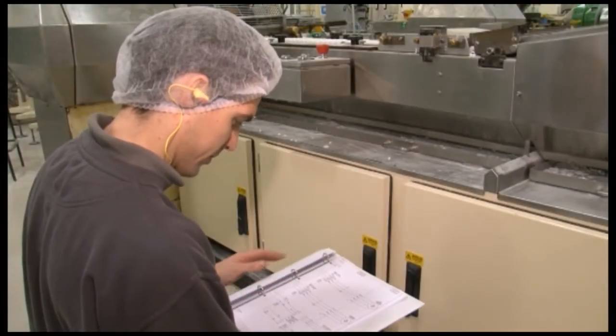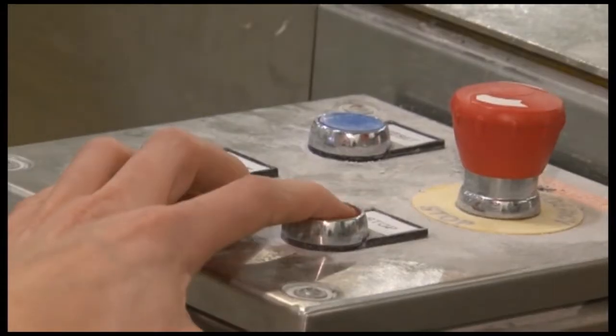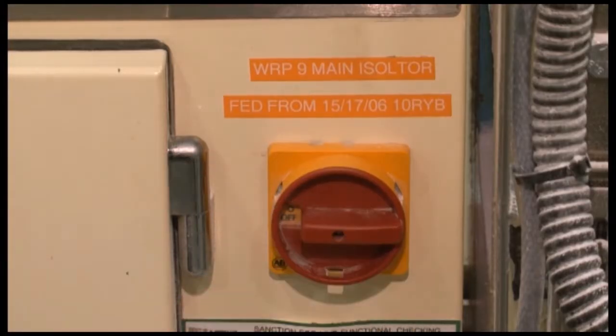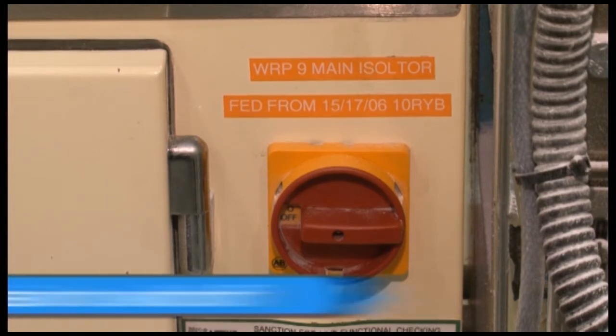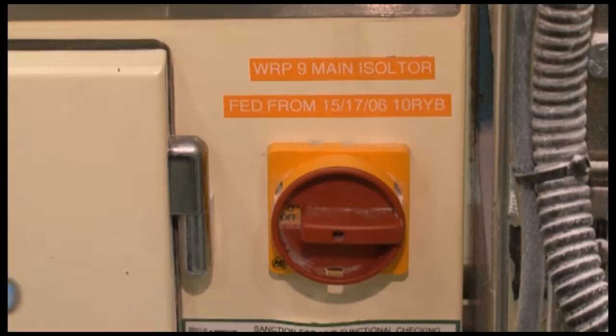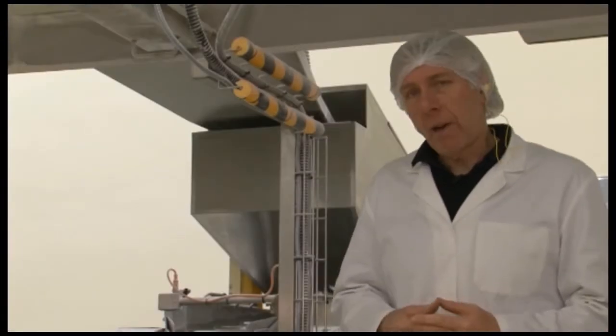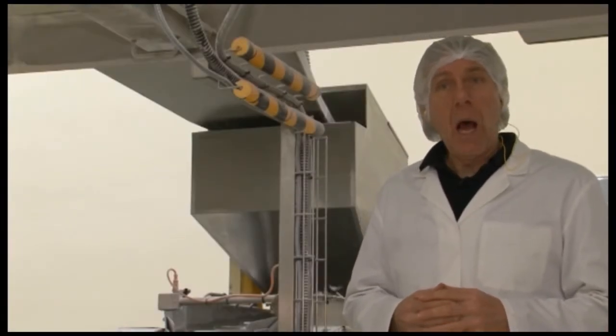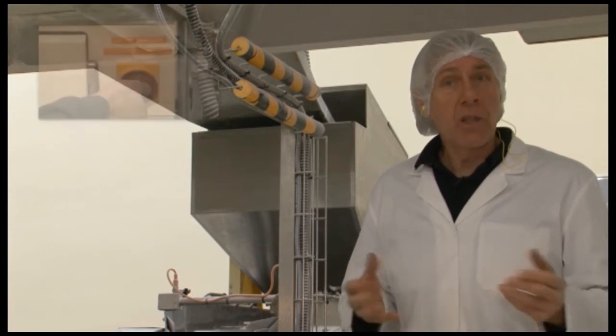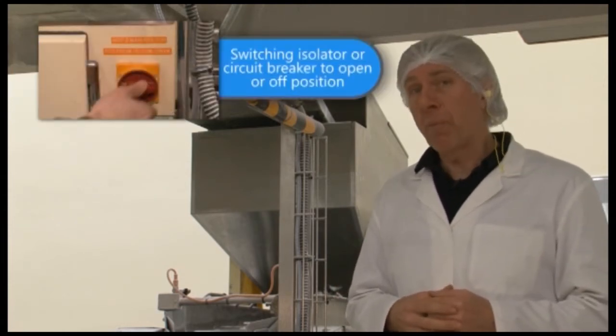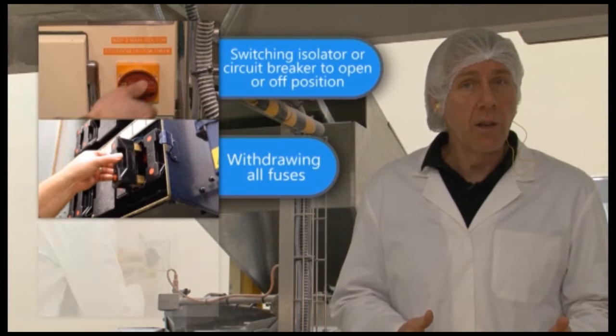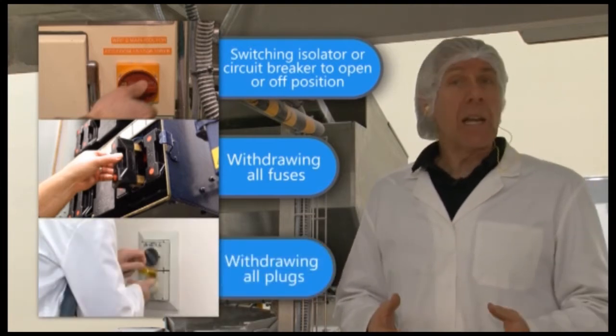If the equipment is still running, you will have to cut off its supply or switch it off before operating the isolator. This is because some isolators are not designed for switching duties. It's also, of course, essential to make sure you have permission to switch off. You may also consider carrying out a risk assessment for any non-electrical hazards, such as surface water. So, having correctly identified and switched off the equipment, isolation can be carried out by switching the isolator or circuit breakers to the open or off position, or withdrawing all fuses, or withdrawing all plugs. The technique used will depend on the supply arrangements to the equipment.